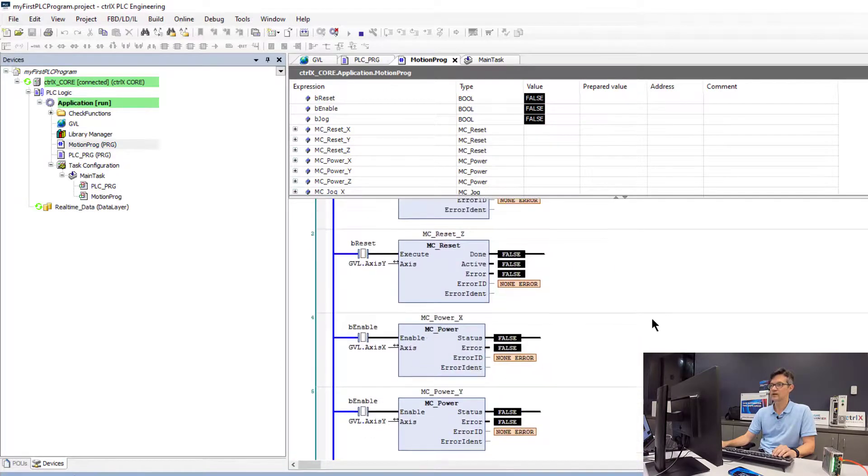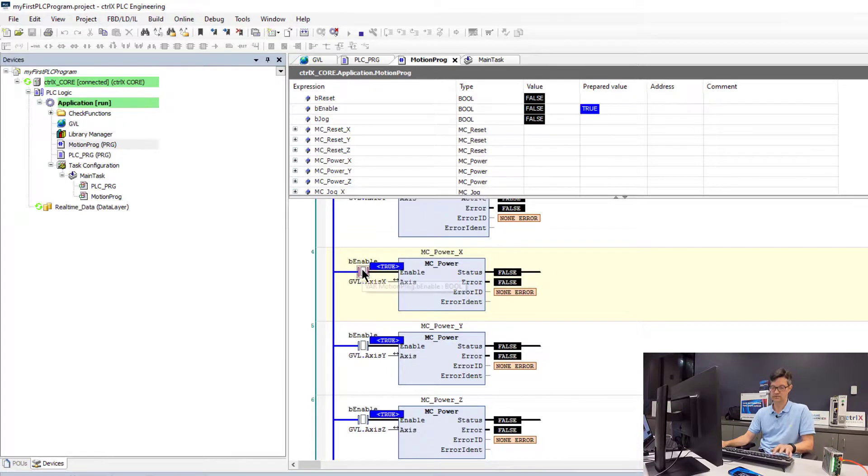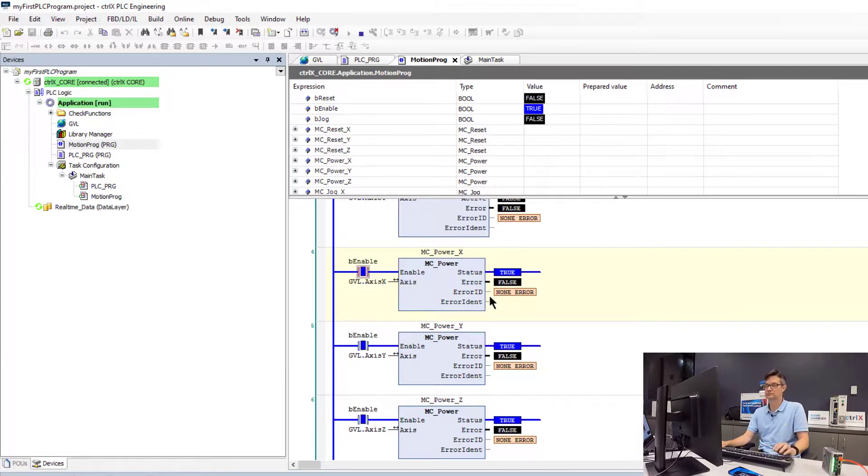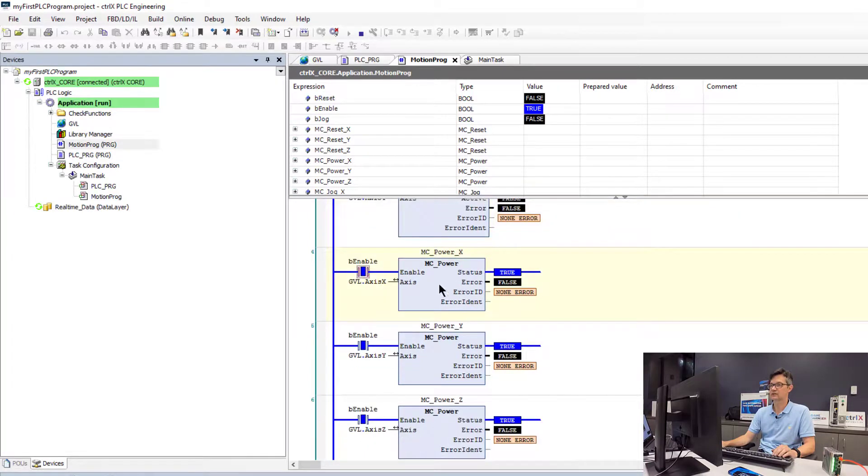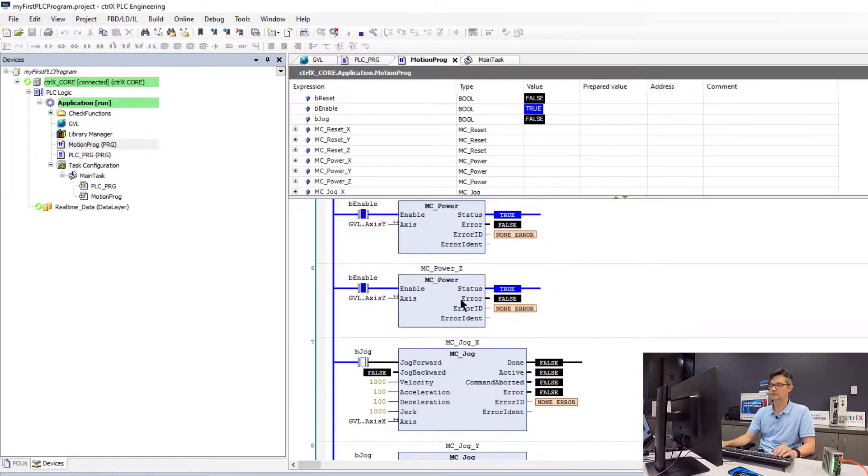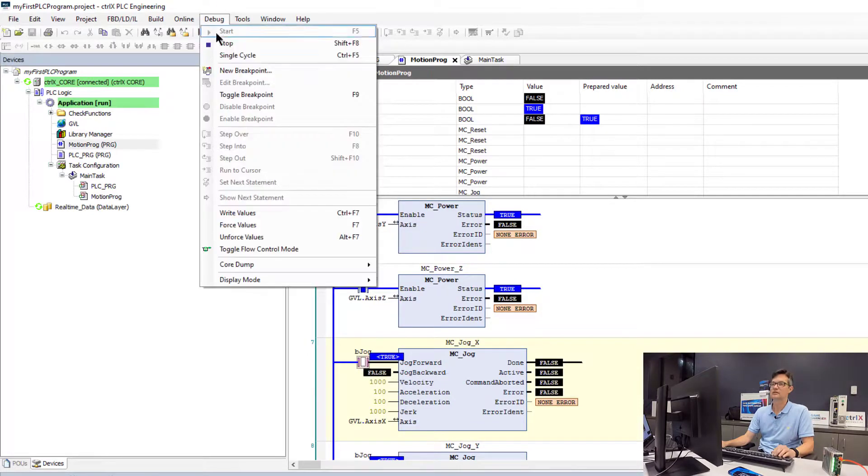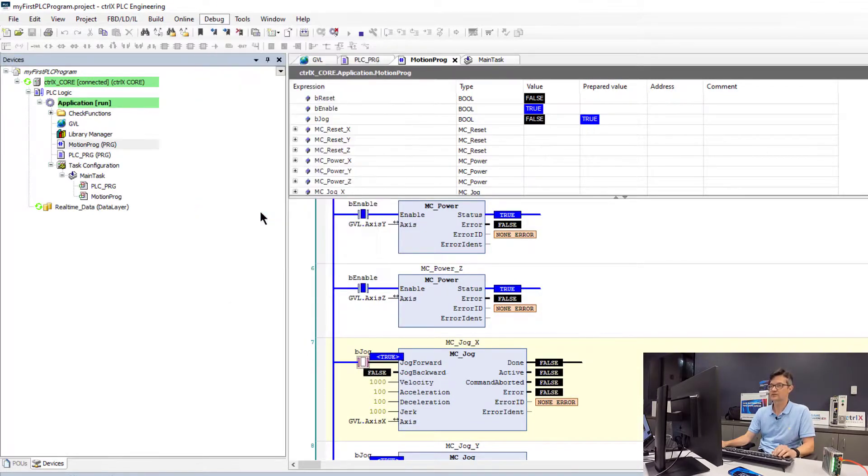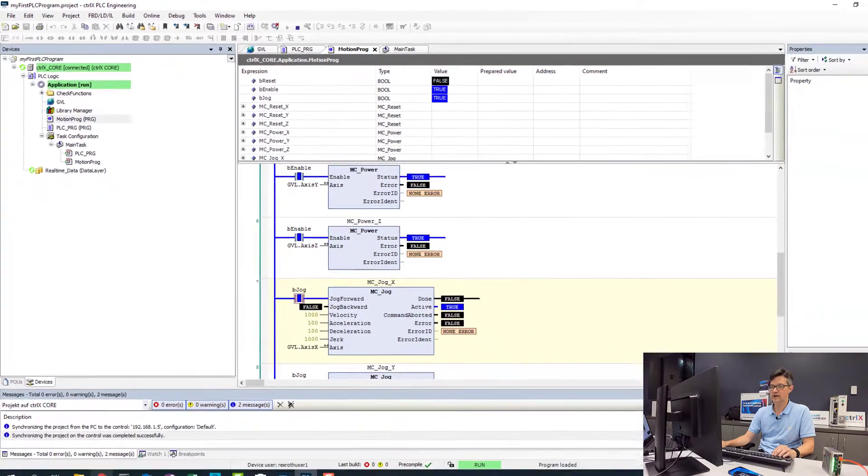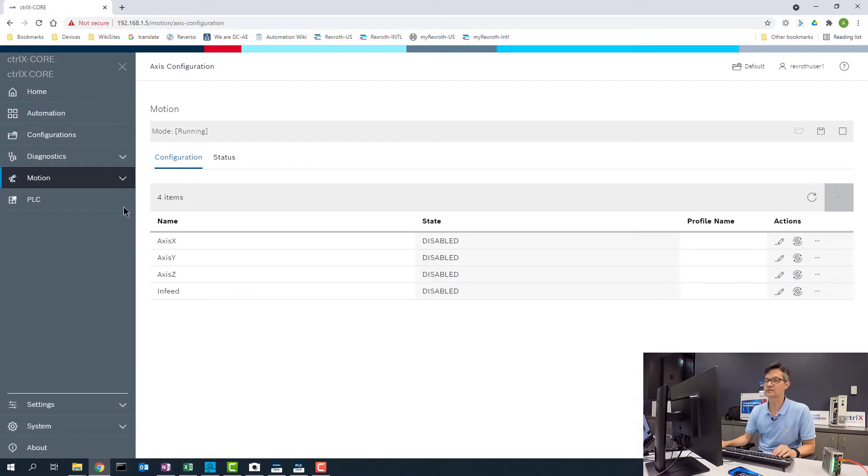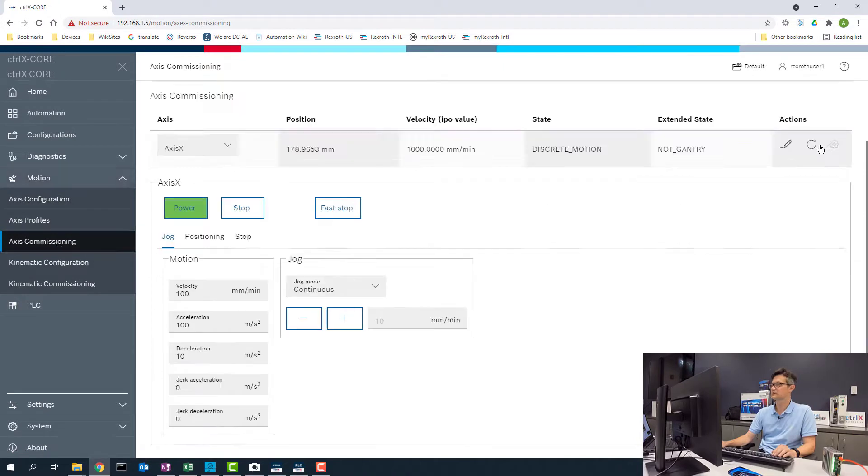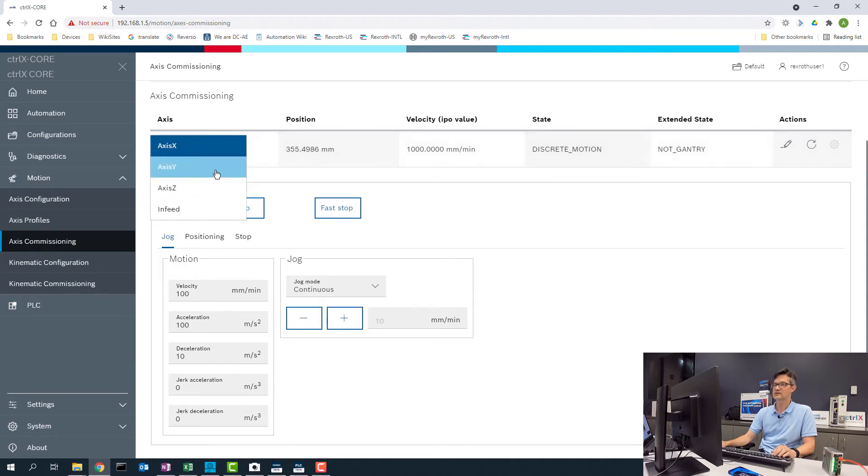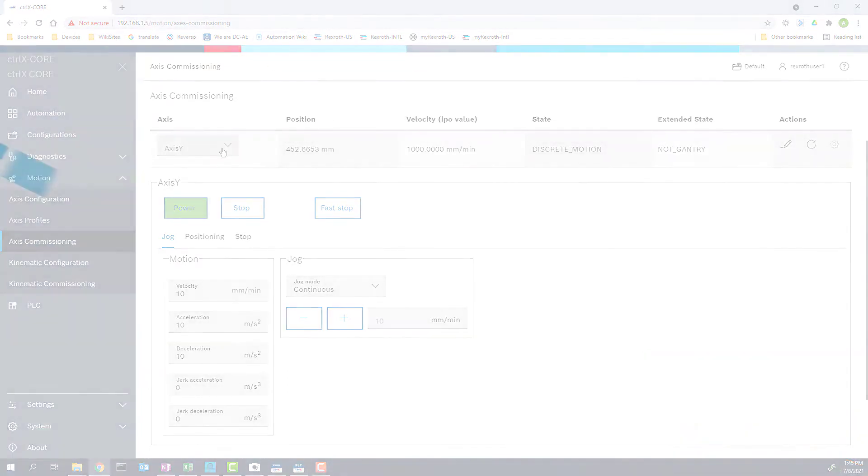So to verify that this works, we will go ahead and turn on the enable. And we will now see that all of our drives are enabled. Write the values to set our jog bit to true. Now our drives are jogging. So we will go back into the application under motion and verify that the axes are moving. So we will go into the axis commissioning screen. Press the refresh values. We were able to see that our X, Y, and Z are now jogging.